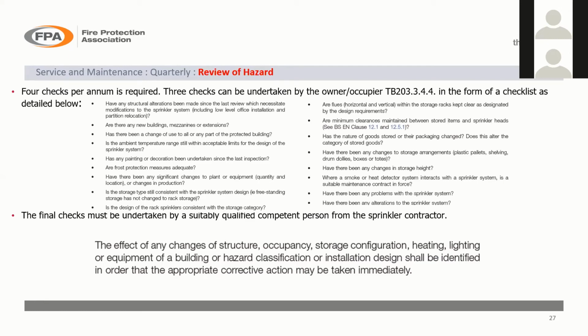Make sure that you haven't done things like put a ceiling in, which has gone underneath the heads. We've seen that happen. So the heads have hit the roof level and they're completely blinded now by the ceiling that's gone in underneath them. People have started to store things higher than was originally envisaged when the building was first built. Have there been any alterations to the sprinkler system? Any of this nature has got to be flagged up on a quarterly basis, and that is one of the things that we noticed hasn't been done.